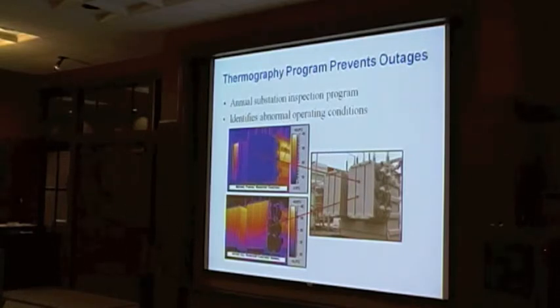And this substation provides power to about half of the main campus, but it also provides power to about half of what the Kauai wastewater plant is selling. So a critical station and a critical transformer. Now, we have an annual program where we use this infrared camera to look around. We look at switches, we look at all the different equipment on there, and we noticed that in this case these fins over here that are used to pump oil out of the transformer, they go through the fins, it's kind of like a radiator on a car, and the fan blows on that, it cools the oil, and brings it back into the transformer and keeps the transformer operating at the appropriate temperature.